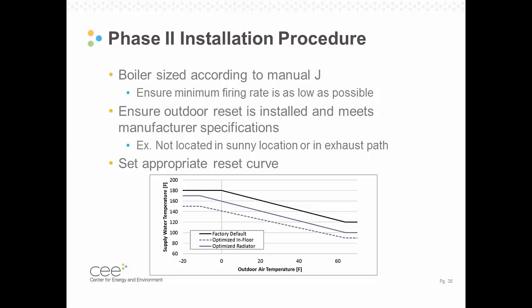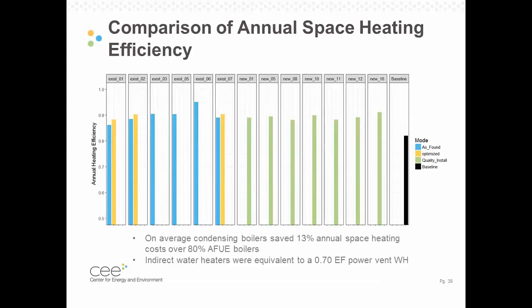And then the big thing is to get that outdoor reset curve, both the outdoor sensor installed in the right spot and the curve set, meeting this slide shown at the bottom of the screen, which really just optimizes based on the emitter type in the home and is typically found in the manual, but here's a general version if it's not available. Looking at the savings from these new install boilers, they're found in green on this slide compared to the as found in blue and the optimized in gold that we talked about previously.